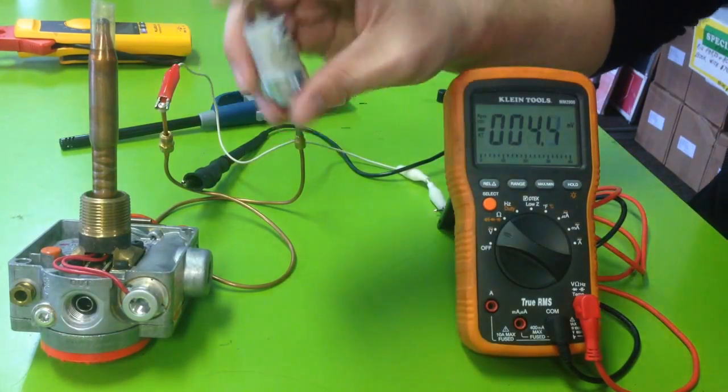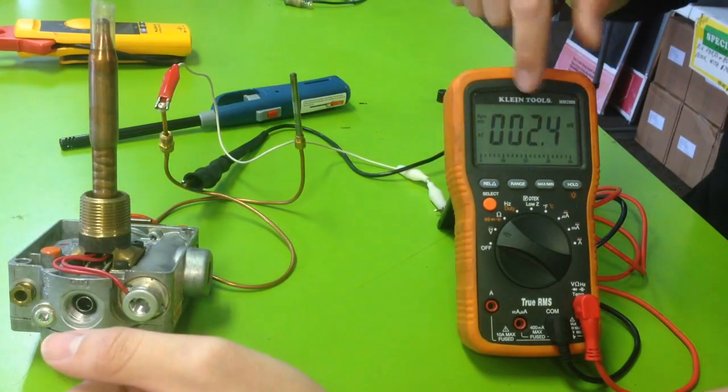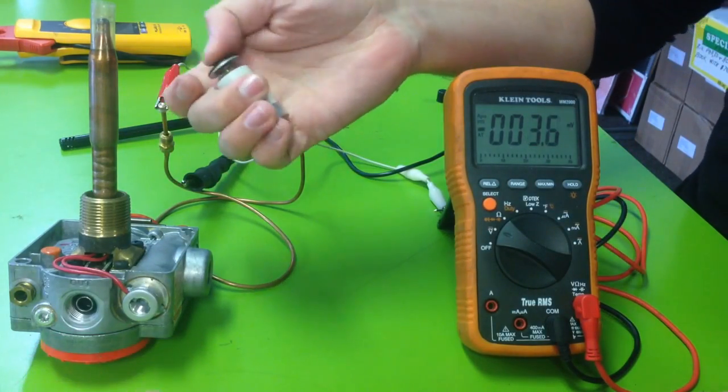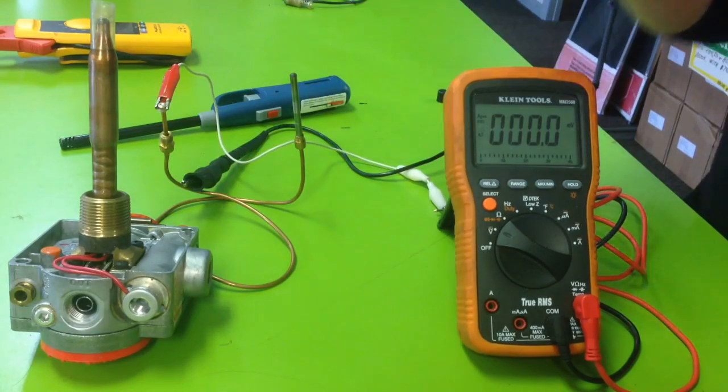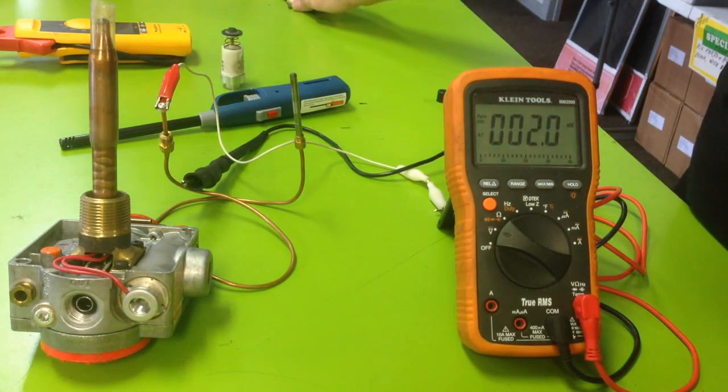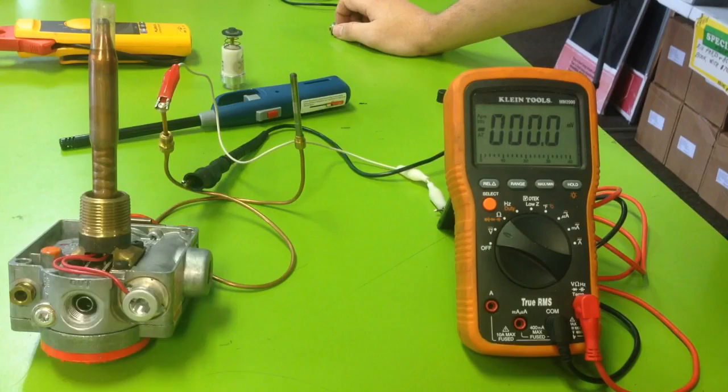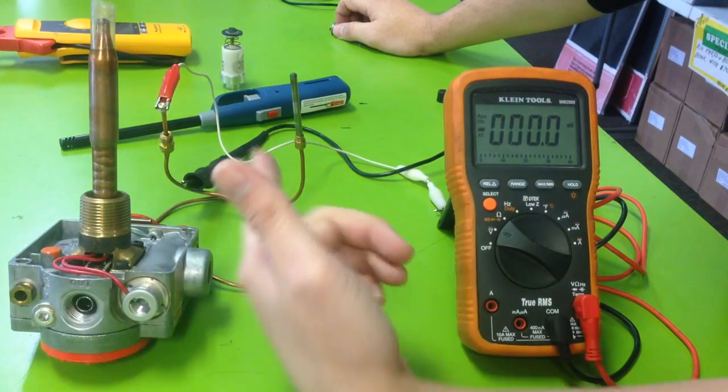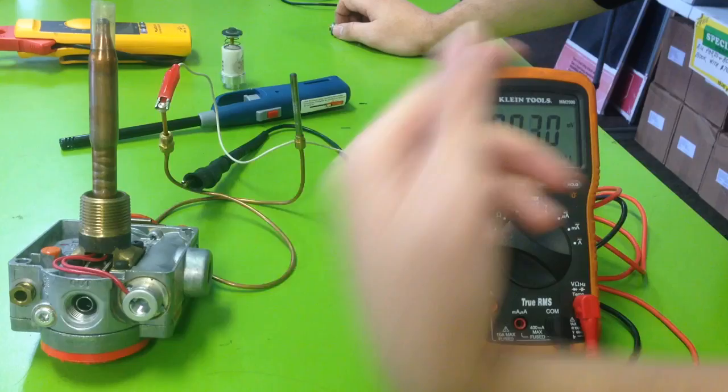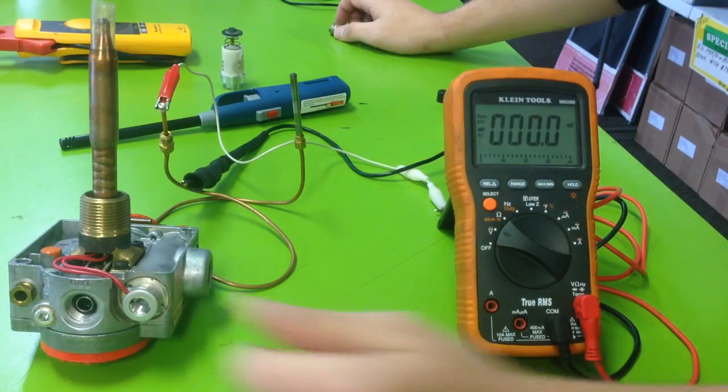You saw in my other video, you can actually buy these thermocoupler testers where instead of looking for a millivolt reading, you just simply see if it holds the valve down. That's a more foolproof way of doing it. But the way you do it with the meter - stupid simple. You just hook it up like I just did and you see if it's generating millivolts. Thanks guys.